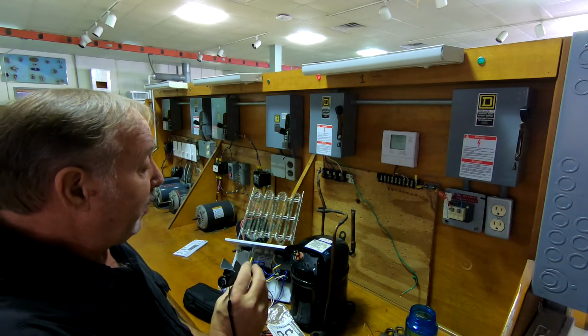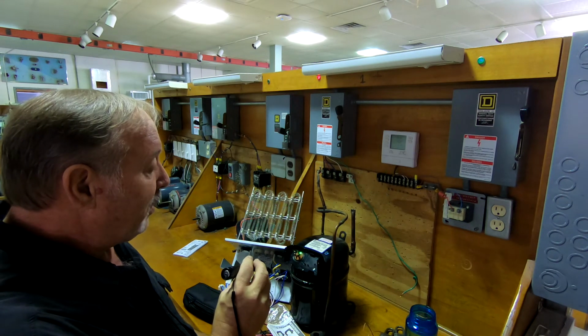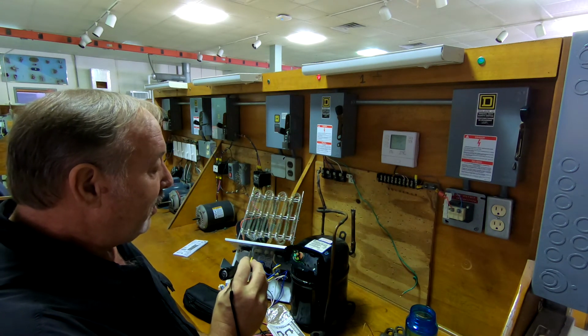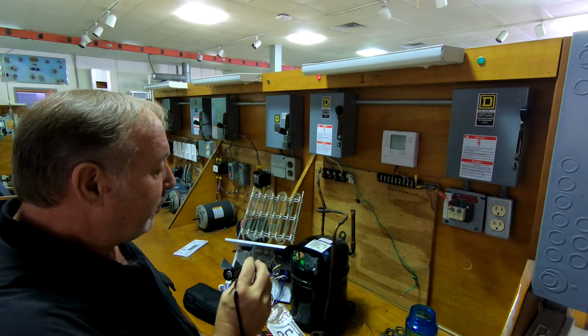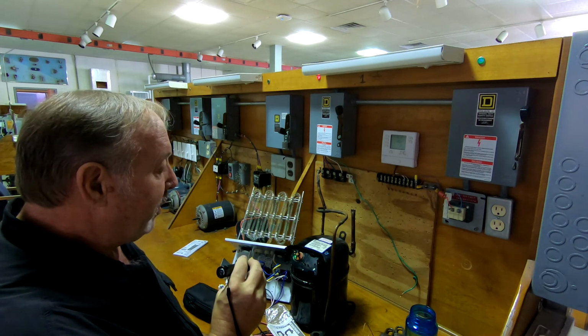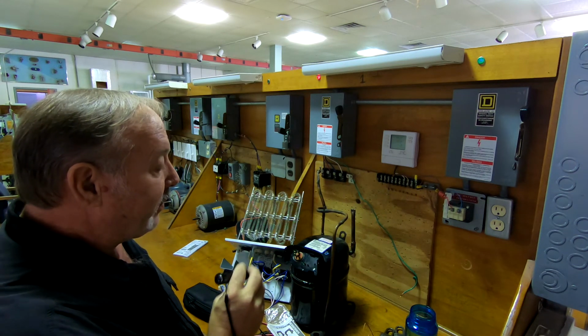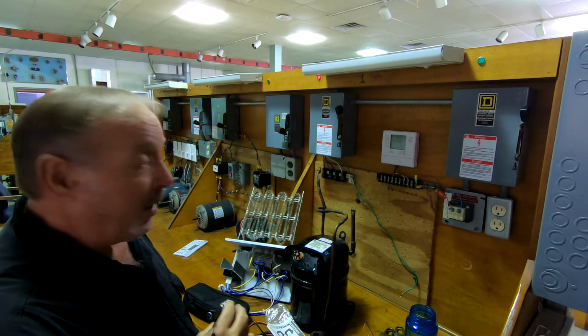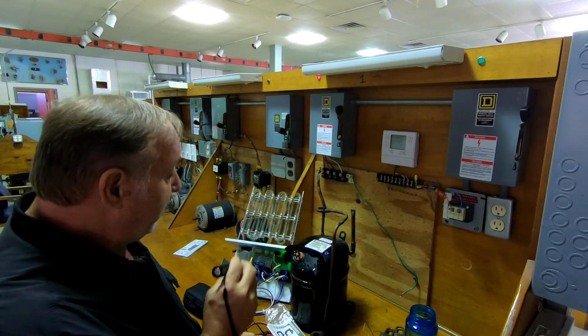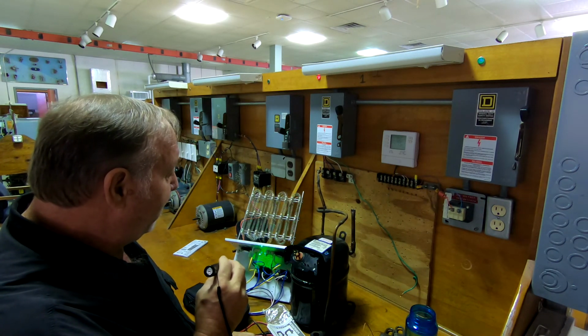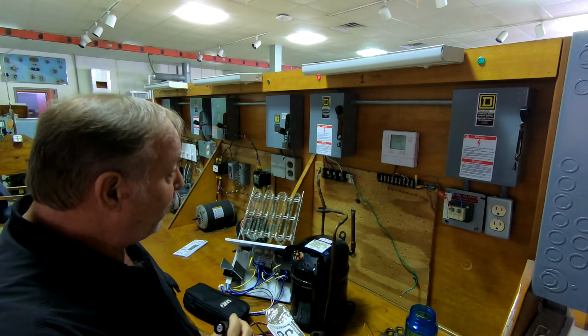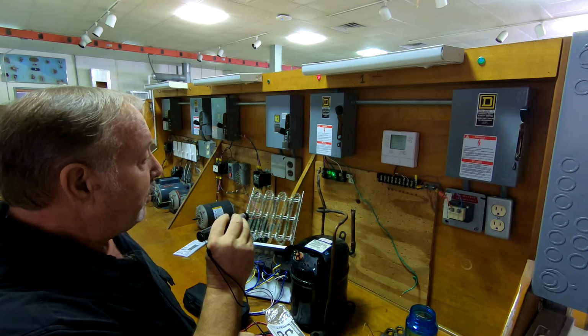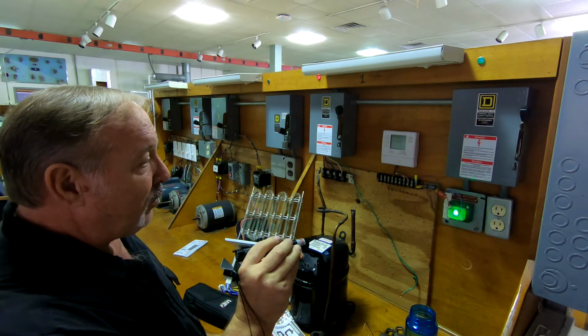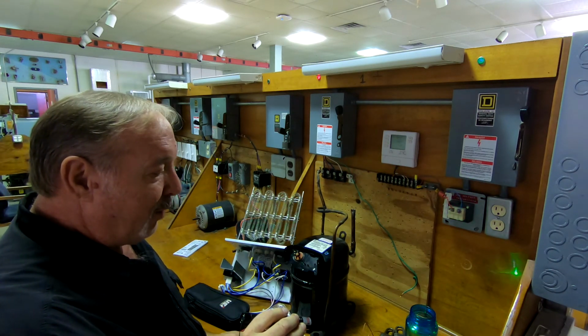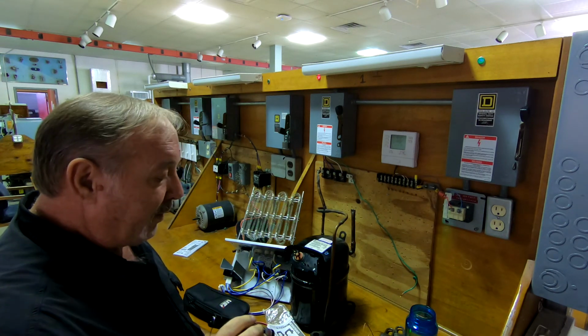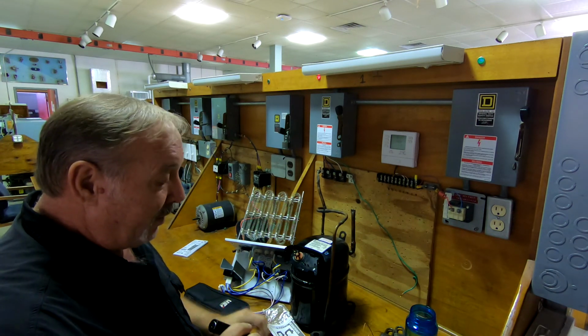So just to give you a reminder, this was the common terminal on the compressor, this was the start terminal, and this was the run terminal. Between the start and the run is the summation of the other two windings. We also tested the two separate elements in the heat strip. We tested the voltage, we tested the low voltage, we tested the temperature of the water, we tested the capacitor, we tested the light bulb.